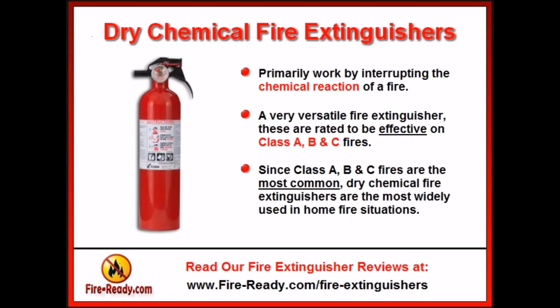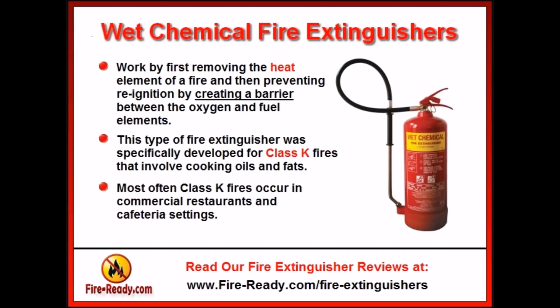Wet chemical fire extinguishers work by first removing the heat element of a fire and then preventing reignition by creating a barrier between the oxygen and fuel elements. This type of fire extinguisher was specifically developed for Class K fires that involve cooking oils and fats. Most often, these Class K fires occur in commercial restaurants and cafeteria settings.